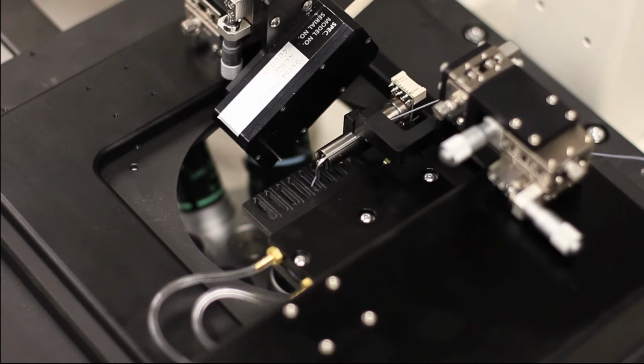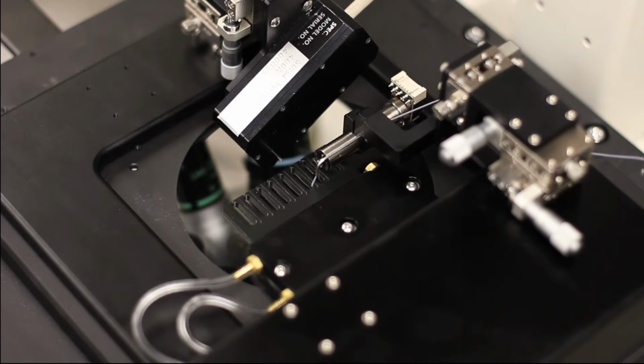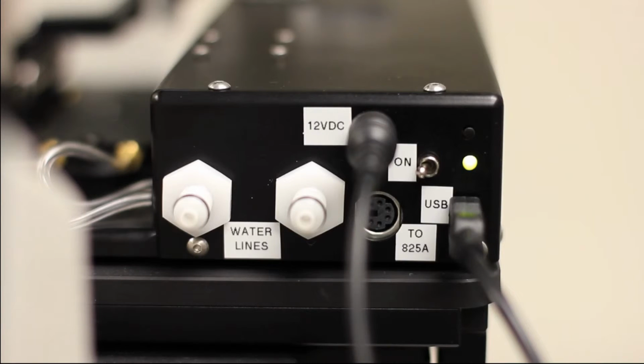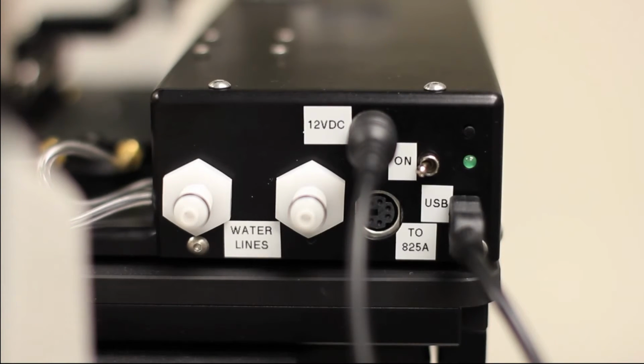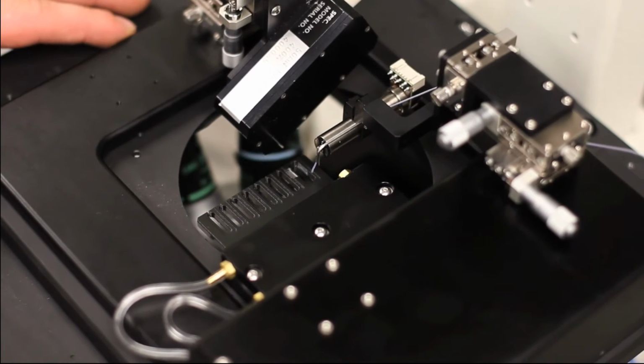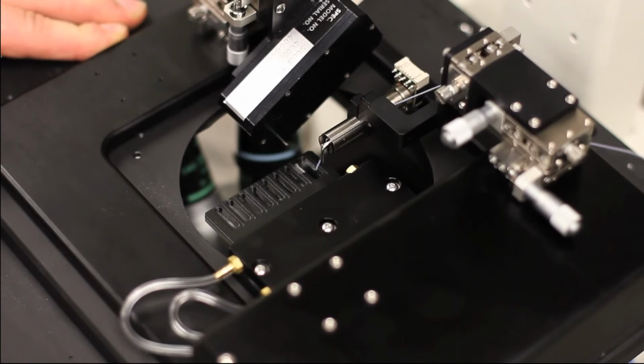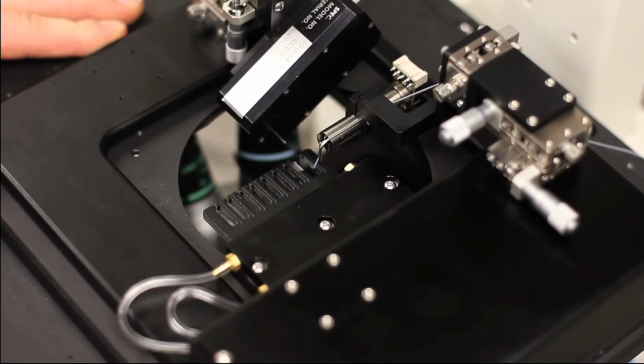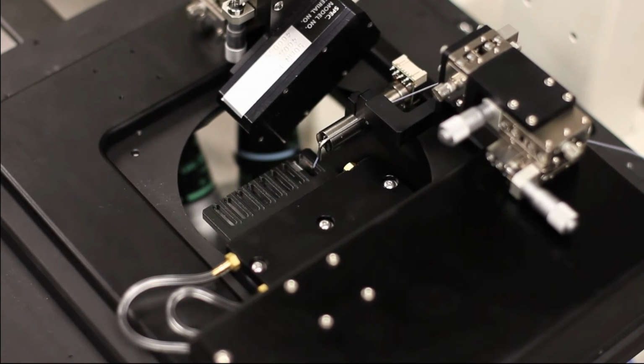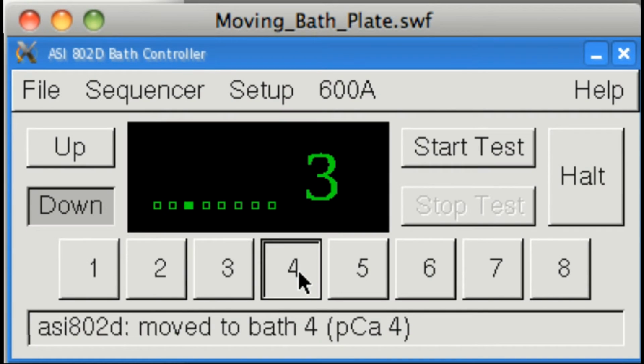If there is interference, then a fault will occur and you will hear the 802D emit a beep and the LED will flash. The fault can typically be cleared by removing any mechanical interference which exists, and then cycling the power switch and restarting the bath control software.